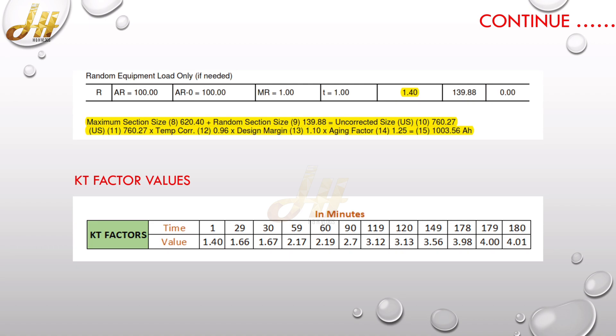Now the capacity has been calculated. Now we will rearrange the KT factor values in an order with time and value. You can see from the above sizing, the value of KT factor for one minute is 1.40, 29th minute is 1.66, 30th minute is 1.67. Similarly, for 60 minute it is 2.19, 120th minute is 3.13, and the third hour, 180 minute, it is 4.01.